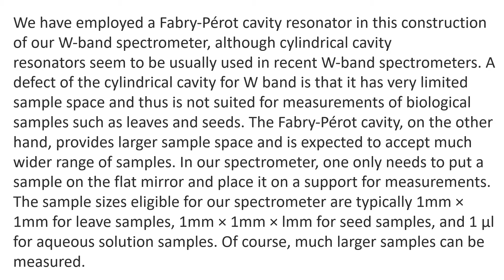The Fabry-Perot cavity, on the other hand, provides larger sample space and is expected to accept a much wider range of samples. In our spectrometer, one only needs to put a sample on the flat mirror and place it on a support for measurements. The sample sizes eligible for our spectrometer are typically 1 mm by 1 mm for leaf samples, 1 mm by 1 mm by 1 mm for seed samples, and 1 µL for aqueous solution samples. Of course, much larger samples can be measured.